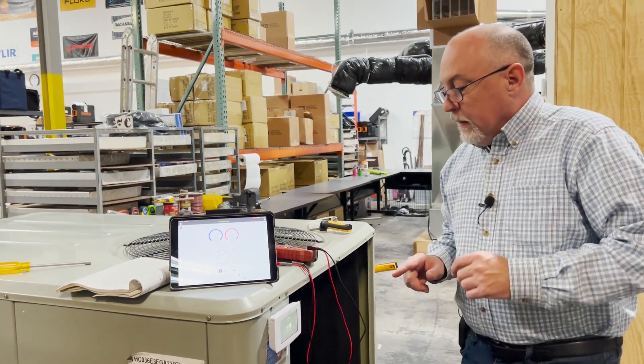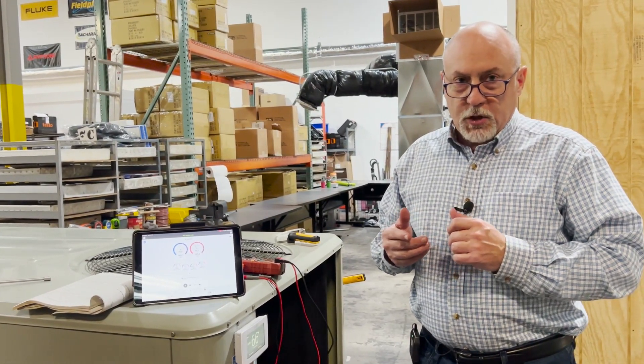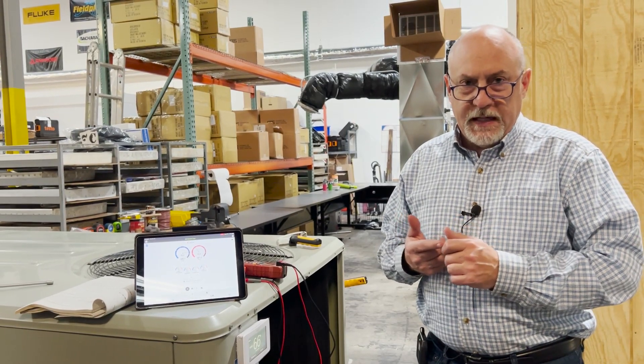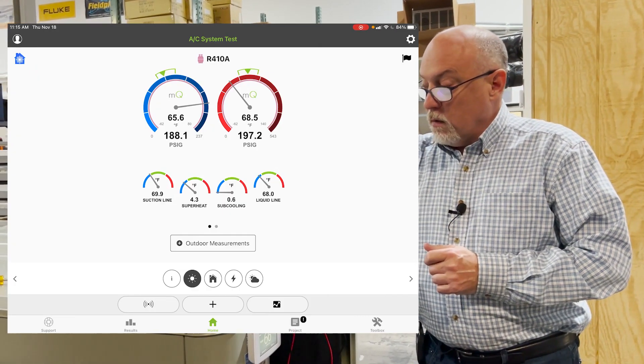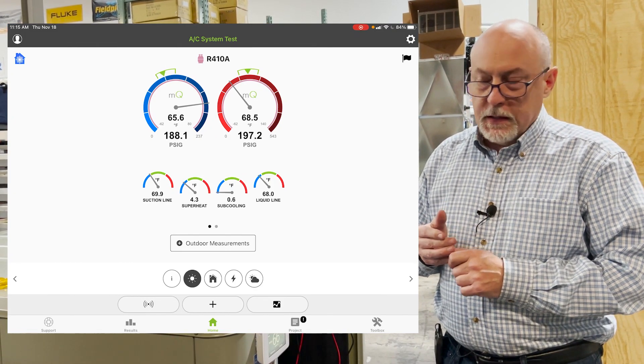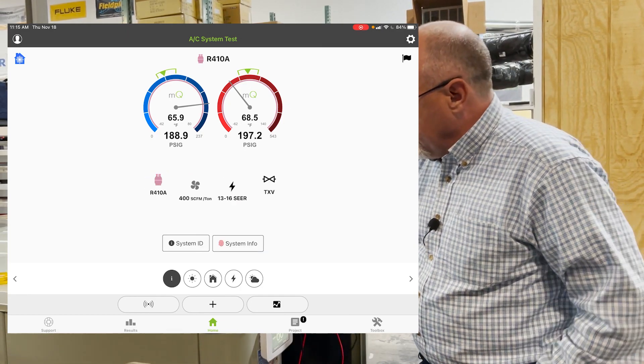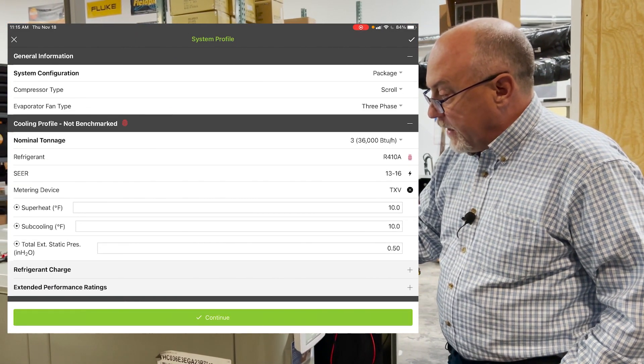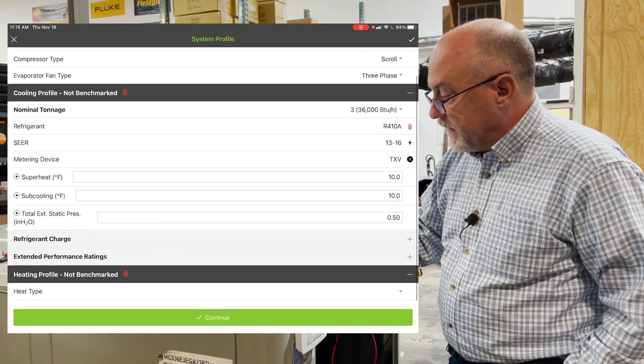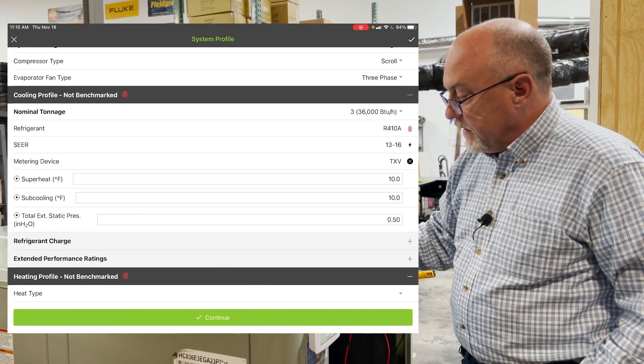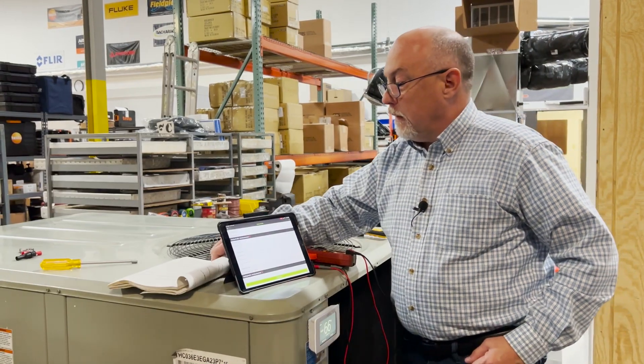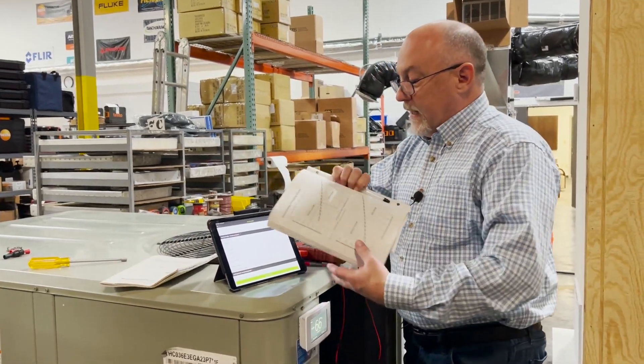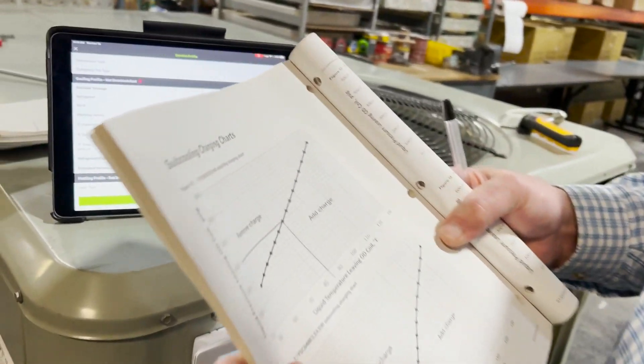Now, in MeasureQuick, we're doing a couple of different things. We're trying to measure the performance of the system. So I want to know what the EER or the SEER is as well as I want to know what my fan watt draw is. So I've got this system profiled here. I'm going to go into the profile just to show you this. And under the system information, you're going to see it's a package unit, three-phase, 36,000 BTUs, 410A. I've got a 13 to 16, and I've got a superheat and sub-cooling set to 10.